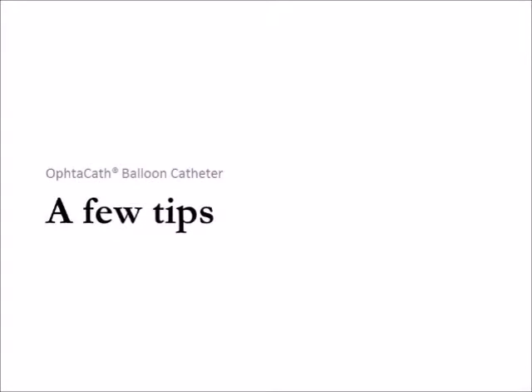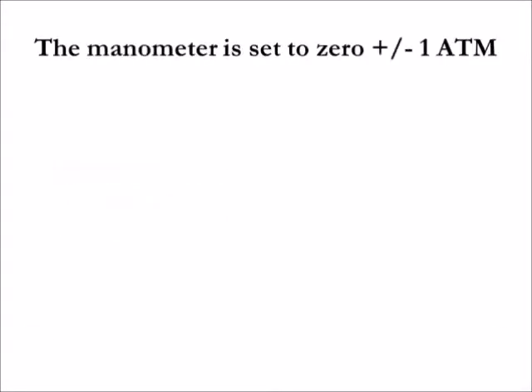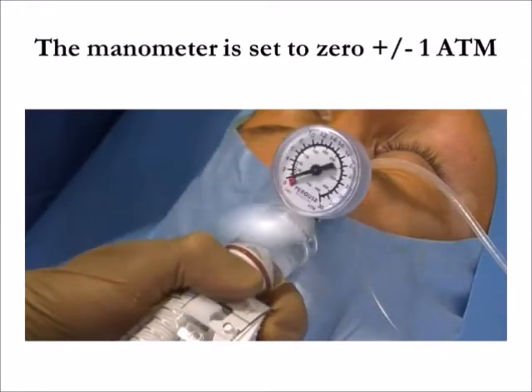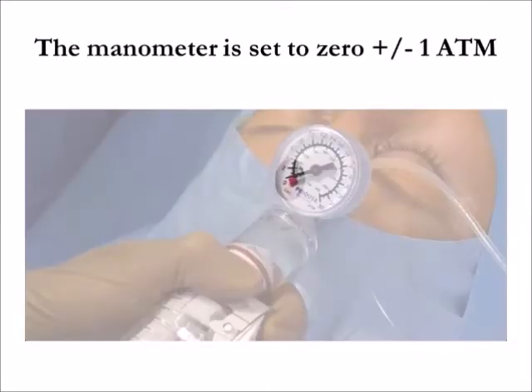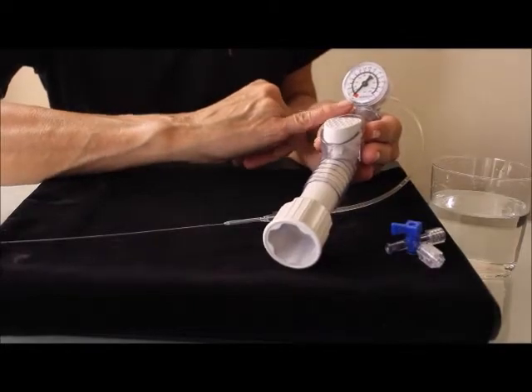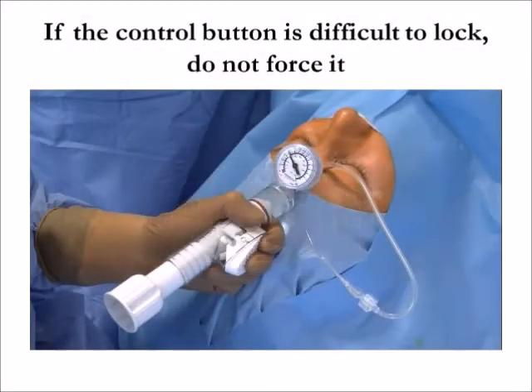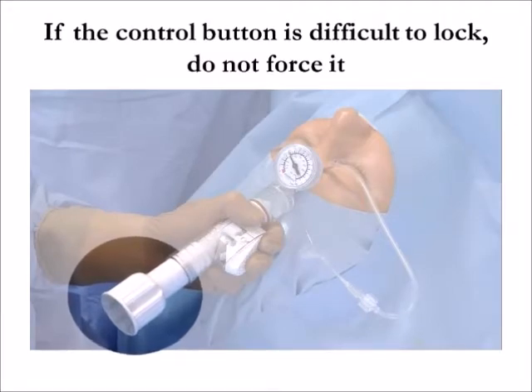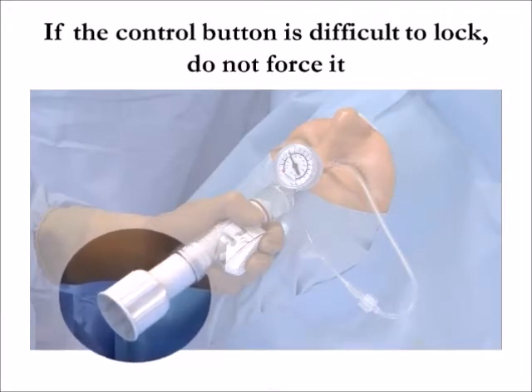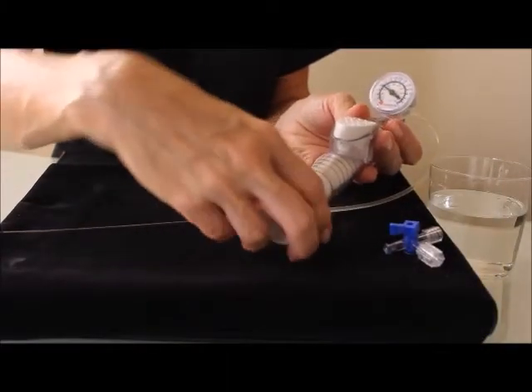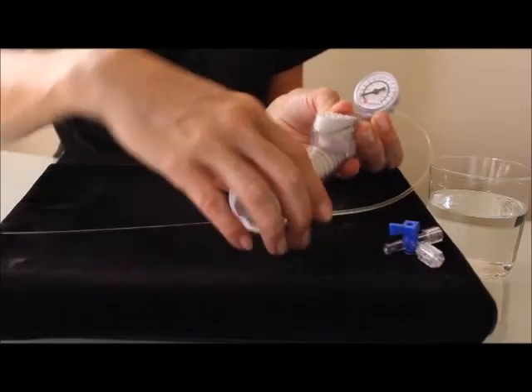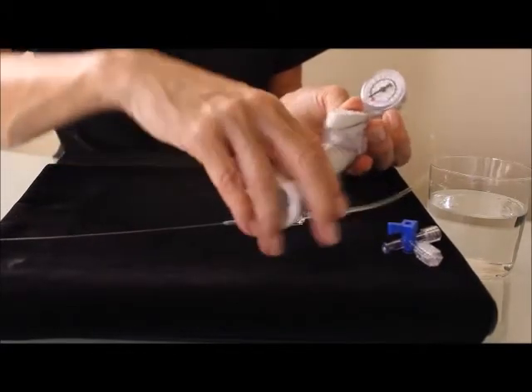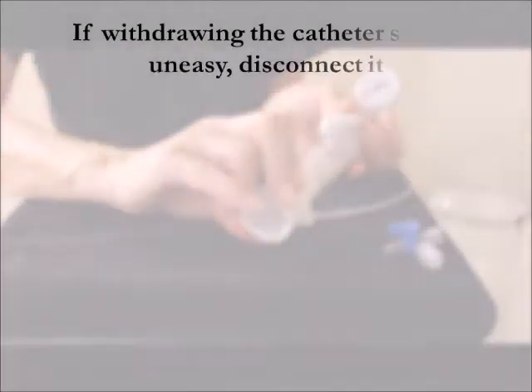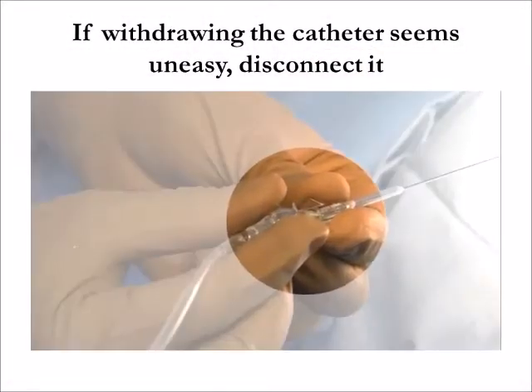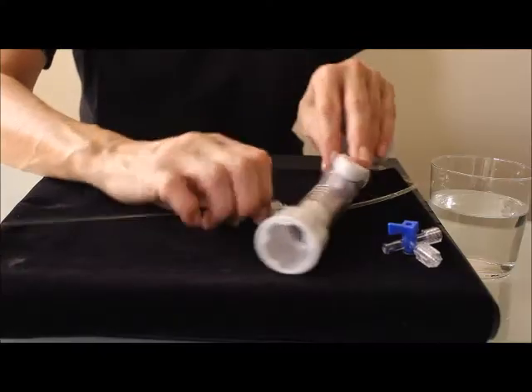A few tips. Before each inflation, confirm that the needle of the manometer is set to 0 plus or minus 1. So in other words, it can't be in the red zone. It's going to be around a 0 or 1. That's okay. You don't want it any higher. If the control button cannot move from the unlock position, turn the rotary handle counterclockwise just slightly to deflate the balloon and then try to lock the device again. If the control button is difficult to lock, don't force it, as this could damage the plunger. Instead, turn the handle gently again, re-engage the control button. Lastly, if withdrawing the catheter seems uneasy, disconnect it from the inflation device by rotating the male luer lock.